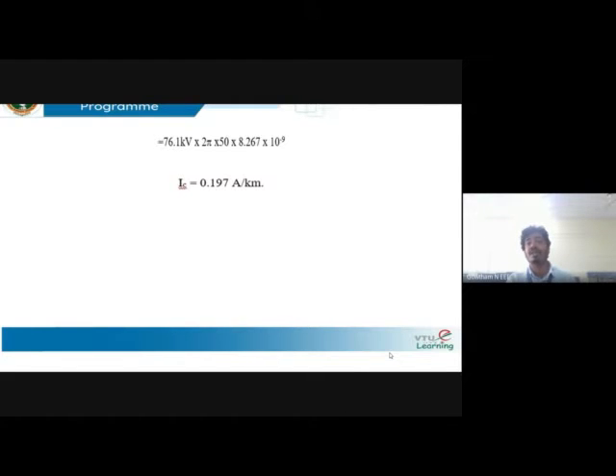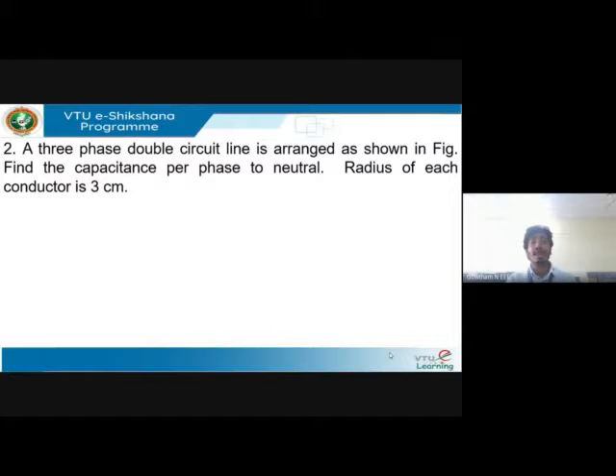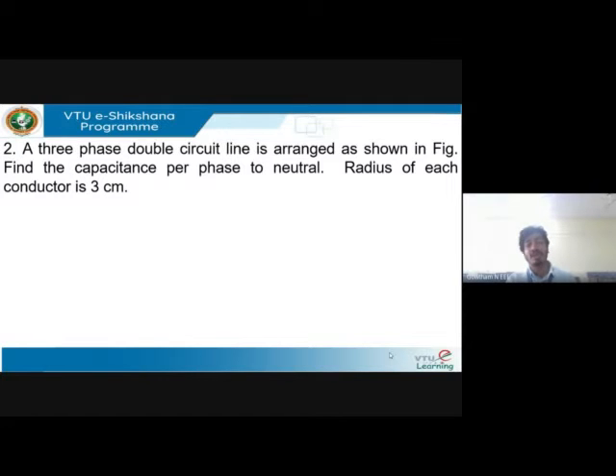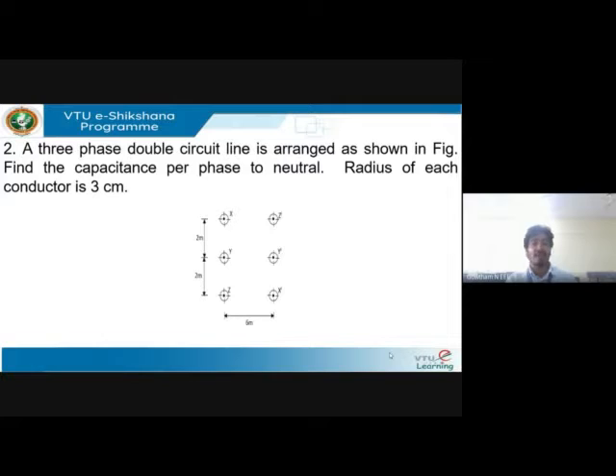On simplification, we get I_c = 0.197 amperes per kilometer. Since they asked for charging current per kilometer, that is the result. Moving on to the next problem: a double-circuit three-phase line arrangement is given and you are to find the capacitance per phase to neutral. The radius of each conductor is given as three centimeters.